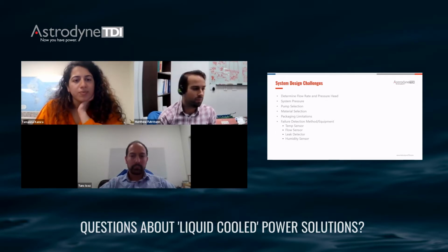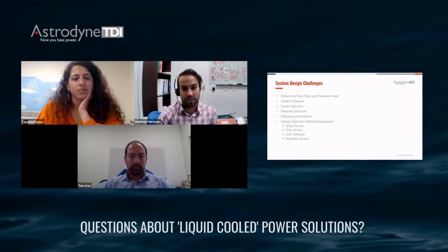a humidity sensor. So I want to explain the purpose of the humidity sensor a little bit. One of the design challenges that we've come across is condensation. And condensation occurs when your coolant temperature is running below the dew point in an uncontrolled climate environment. Now, the dew point is a function of the relative humidity and your ambient temperature. And condensation can build on the surfaces of your cold plate, and over time, that condensation can cause damage to electronics if not properly mitigated. So one of the solutions that we've come up with involves humisealing our PCBs.